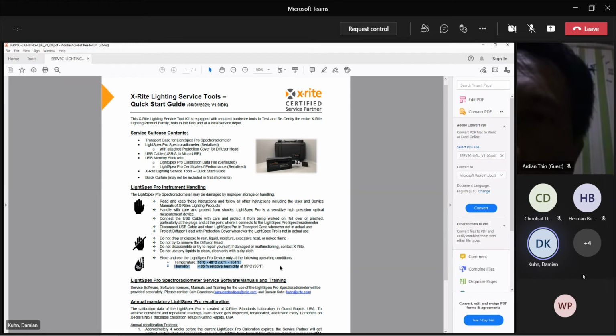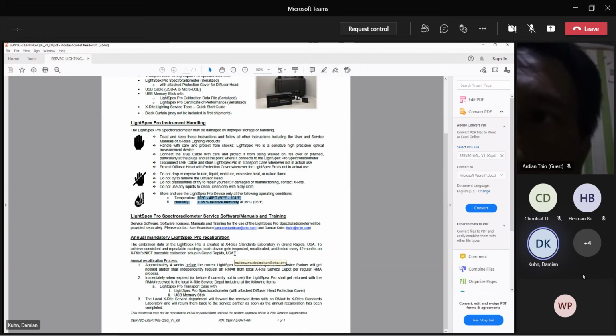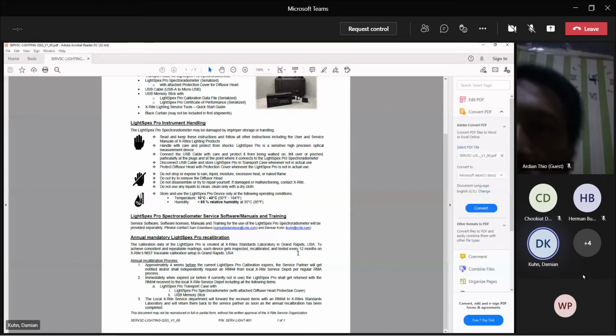Additional information you have, as well, is at the bottom of the quick start guide. So we're talking about what needs to happen when the instrument requires recalibration. In that case, it's a similar process to the old Lightspex instrument. You would simply request an RMA, in your case, from the Hong Kong service department, and then the instrument would get returned via Hong Kong to the service headquarters in the US, where we recalibrate the instrument, create a new calibration file and a new instrument certificate, and then that would be returned via the Hong Kong service department back to you.